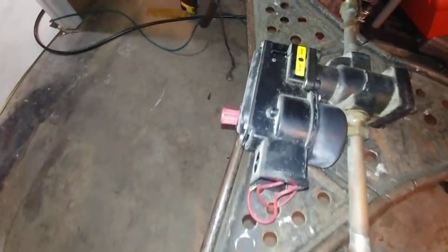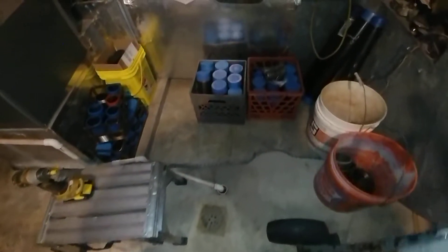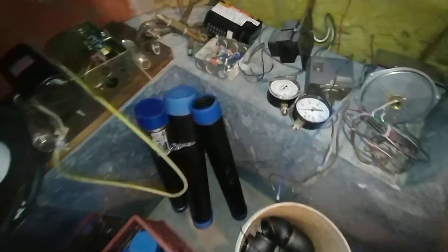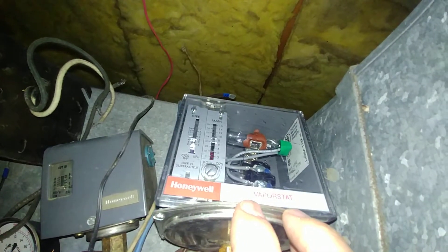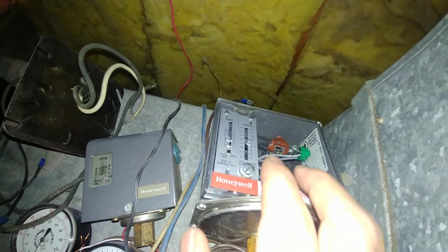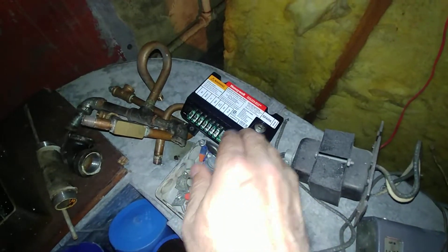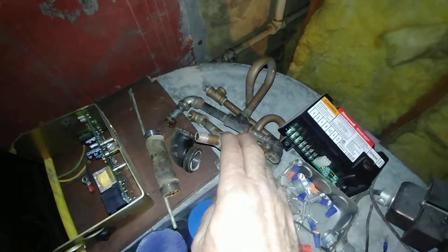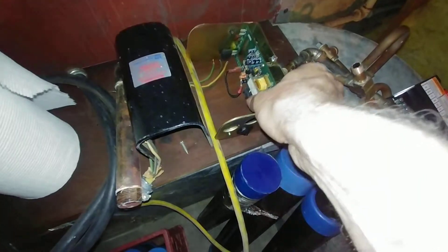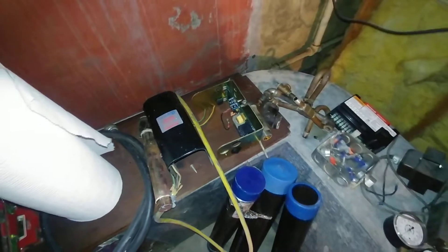We originally had a low-pressure gauge, and we reinstalled a vapor stat down to one-eighth ounce, and upgraded this to a spark module with proper pigtails. We also had a McDonnell Miller electronic low water cut-off backing up the number 67.